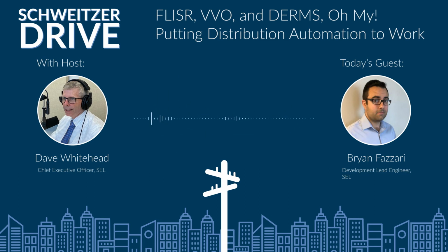So we start adding reclosers and sectionalizers to the feeder. After that, I want to minimize reactive power flow for large customers or all customers, so I'm going to put capacitor banks all over the feeder to provide VARs close to where they're needed. So we put protective devices close to where they're needed, VARs close to where they're needed. I want to reduce my peak loading on feeders, so I'll start connecting solar facilities, microgrids, batteries, so that we're reducing peak power close to where it's needed.